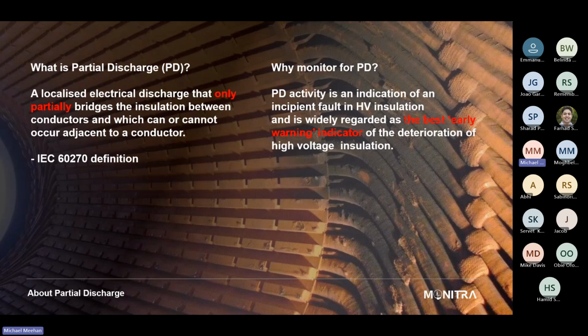So the PD activity, depending on the severity of the pulses and the accumulation of the pulses, all provide an indication of the type of problem that might be or might not be present in the machine. There's never a definitive time to failure with PD, but there is a more likely versus less likely type approach when we provide the data and when the analysis is complete. And based on the PD patterns, which we do touch on later, there is a strong correlation between certain patterns and definitive failure modes. It's so well established now that anyone who is provided a PD report with a particular failure mode present on a PD pattern will act upon it. But they'll be able to do that in such a time frame where they can probably wait for an outage or an appropriate window where there's less impact to production and operations. So the cost of any remedial actions is controlled.